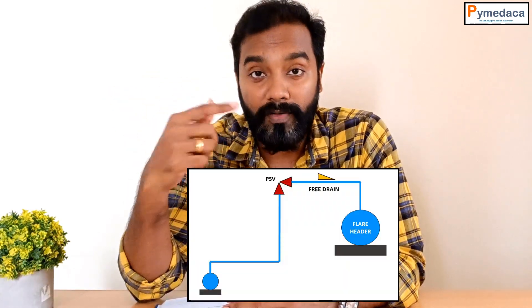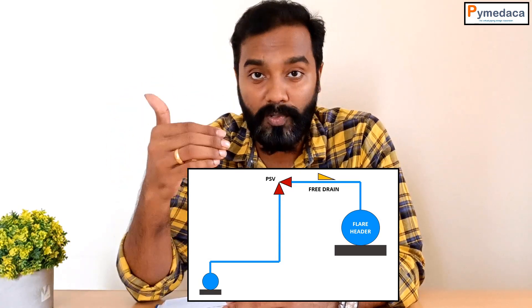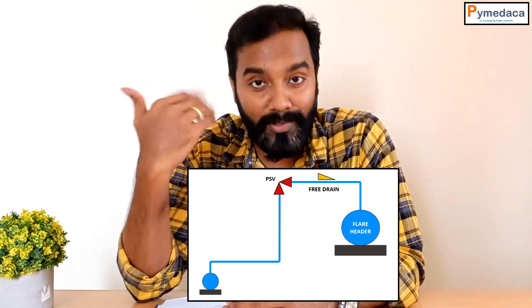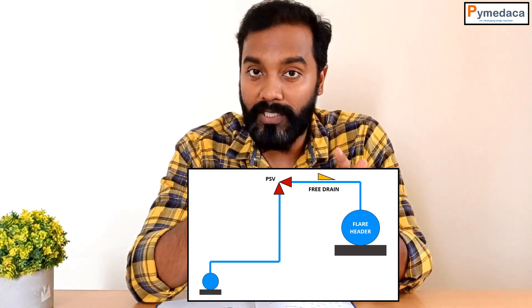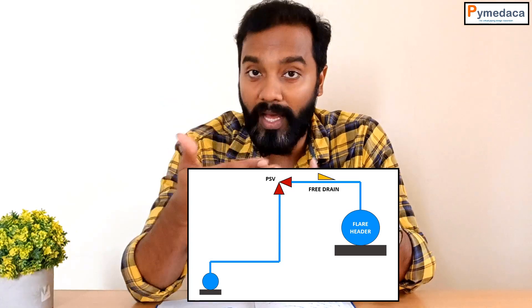The third point is: why do we place a PSV always on top, or above the flare header? That is because the downstream PSV piping should have a free-draining facility. To achieve free draining, the PSV must be placed above the flare header; otherwise, free draining will not occur. So you must install the PSV above the flare header in your process plant.